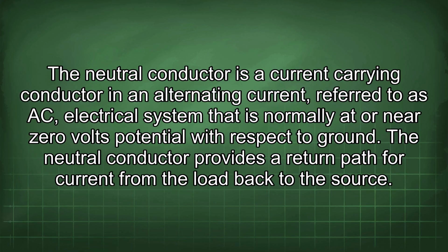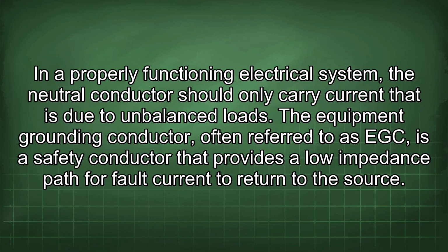The neutral conductor is a current-carrying conductor in an alternating current, referred to as AC, electrical system that is normally at or near 0 volts potential with respect to ground. The neutral conductor provides a return path for current from the load back to the source. In a properly functioning electrical system, the neutral conductor should only carry current that is due to imbalanced loads.